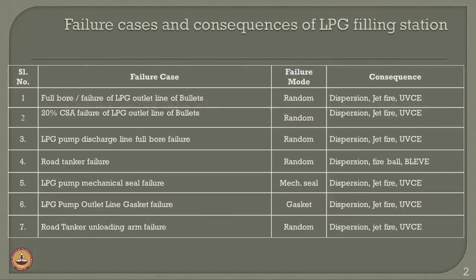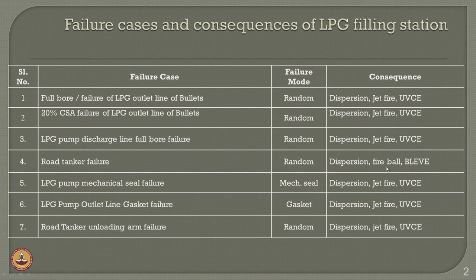In the last lecture, we discussed the different failure cases and consequences of a case study of an LPG filling station located at two different geographic places. Different failure cases were identified: full bore failure of the LPG outlet line of bullets, 20 percent cross-section area of failure, LPG pump discharge line full bore failure, road tanker failure, LPG pump mechanical seal failure, LPG pump outlet line gasket failure, and road tanker unloading arm failure. The consequences could be dispersion, jet fire, vapor cloud explosion, BLEVE, and fireball. We discussed dispersion and jet fire in the last lecture.